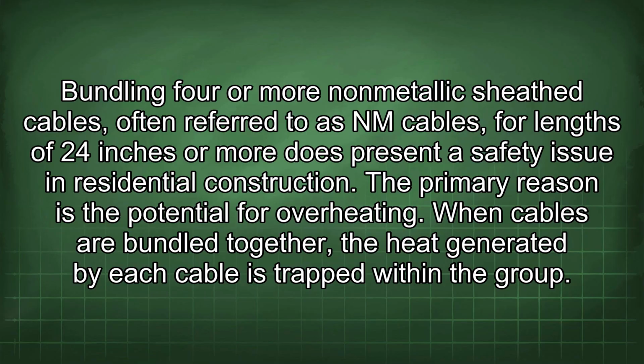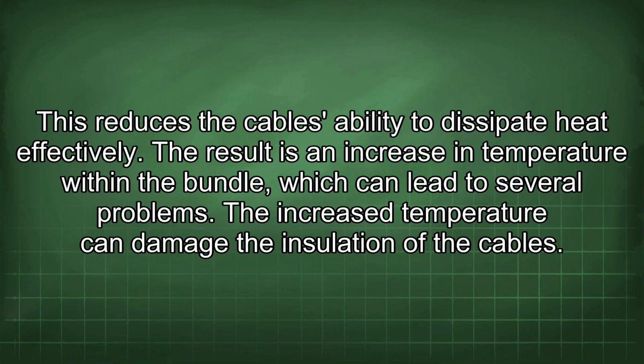Bundling 4 or more non-metallic sheath cables, often referred to as NM cables, for lengths of 24 inches or more does present a safety issue in residential construction. The primary reason is the potential for overheating. When cables are bundled together, the heat generated by each cable is trapped within the group. This reduces the cable's ability to dissipate heat effectively. The result is an increase in temperature within the bundle, which can lead to several problems.